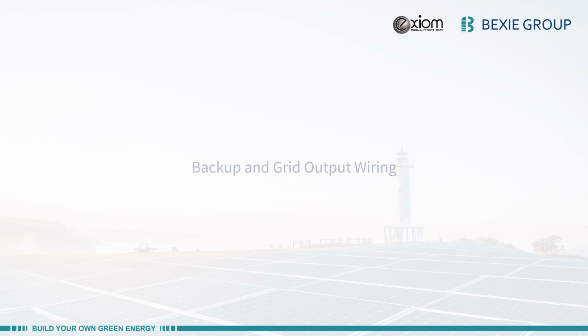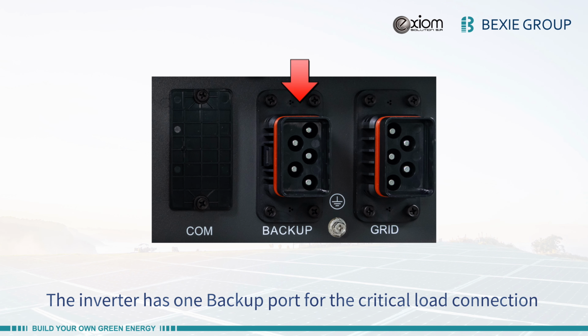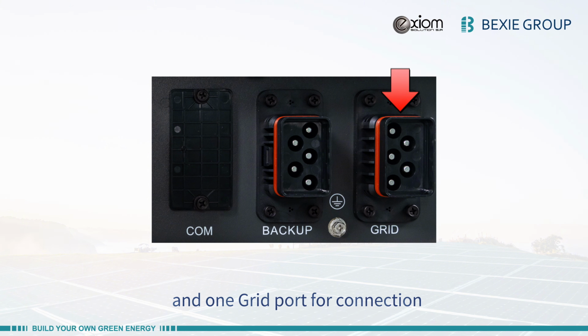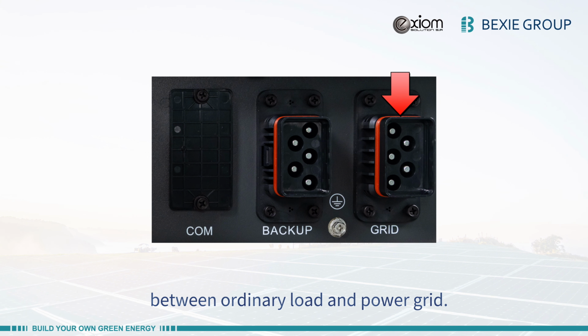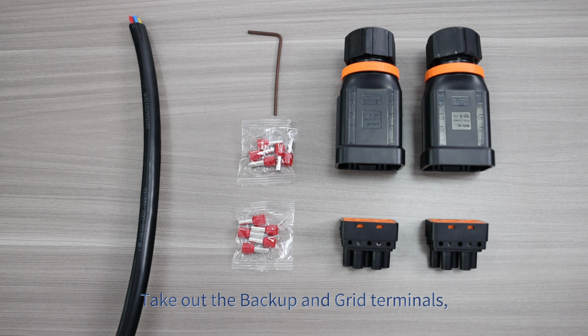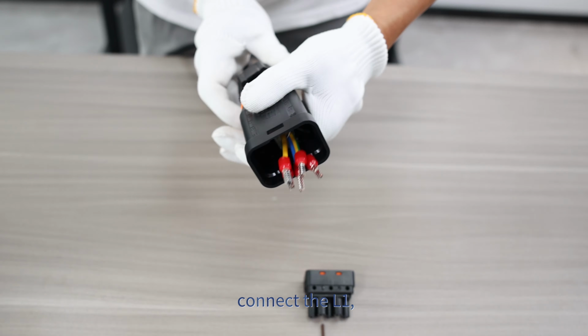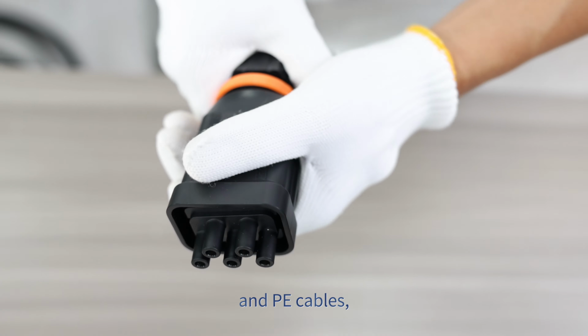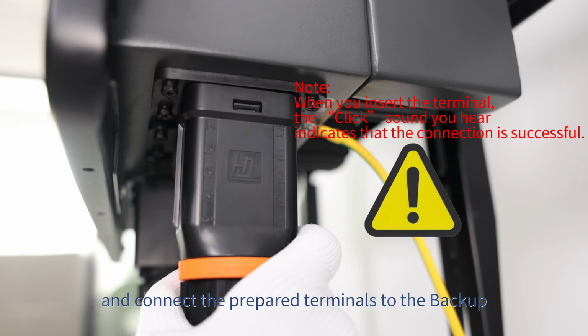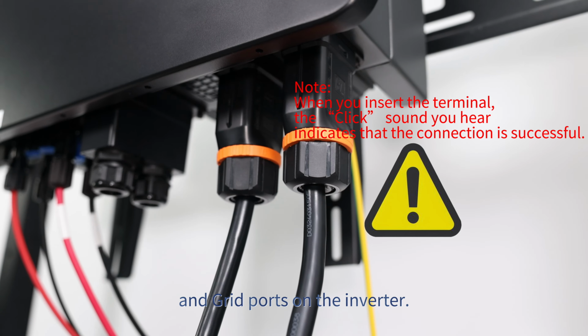ports of the inverter. Backup and grid output wiring. The inverter has one backup port for the critical load connection and one grid port for connection between ordinary load and power grid. Take out the backup and grid terminals, connect the L1, L2, L3, N, and PE cables, and connect the prepared terminals to the backup and grid ports on the inverter.